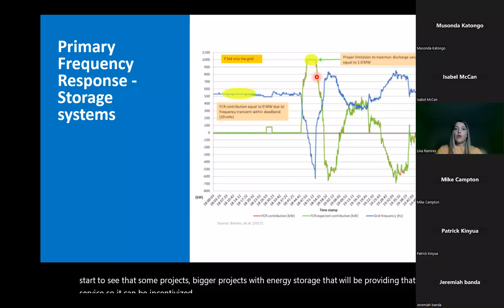So that's the case of the market product, and it's the same case for ERCOT. They start to request fast frequency response - they act in less than 1 second and should maintain the response for 15 minutes. They allow IBR, synchronous generation, and also demand to participate in that product. So again, it's a product helping them maintain the critical inertia levels they need to avoid any frequency problem.